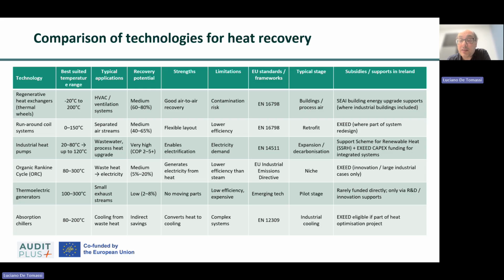improvements. Run-around coil systems are generally used where supply and exhaust air streams are physically separated and cannot be connected through a conventional heat exchanger. Run-around coil systems recover heat by circulating a fluid, typically water or a water-glycol mixture, between a coil in the exhaust air stream and a coil in the incoming air stream, transferring heat without mixing the air streams, and are typically used for temperatures ranging from about 0 Celsius degrees to 150 Celsius degrees and achieve heat recovery rates of approximately 40% to 65%.